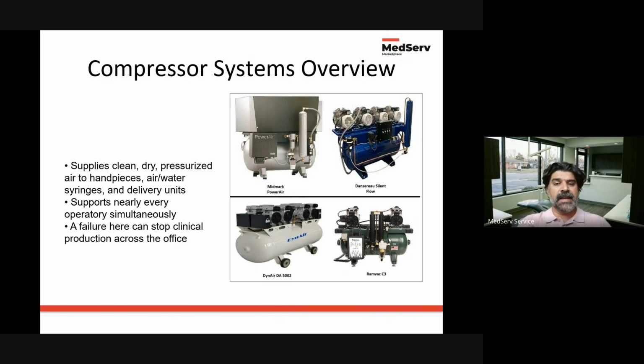And so a lot of the time, working on these systems involves a PM where you're replacing filters. You are servicing the desiccant dryers for the air compressor, making sure that it's able to pull out all the moisture before it goes into the facility itself. A lot of times you'll notice some condensate will accumulate in tanks, so you want to make sure that those can be drained. These are all different checks that are done on a PM schedule.